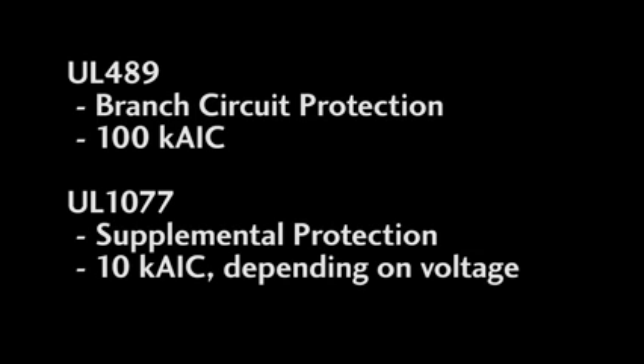The UL rating depends on your requirements. 489 devices are specifically designed for and rated to protect branch circuits, including conductors, control panels, switchboards, motor control centers, things like that. The 1077 devices are strictly supplemental and should only be used where branch circuit protection is already provided and you just want some extra protection, or where protection is not required but you want to add some anyway. The 489 devices can handle up to 100,000 amps of interrupt capacity. The 1077 devices are in the tens of thousands of amp interrupt capacity, depending upon what voltage you use them at.